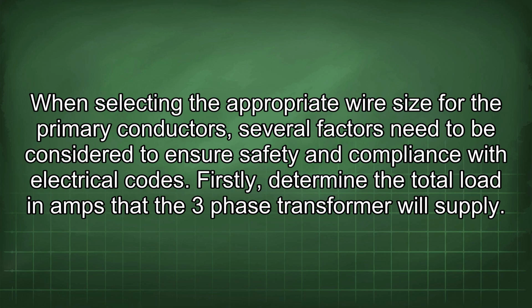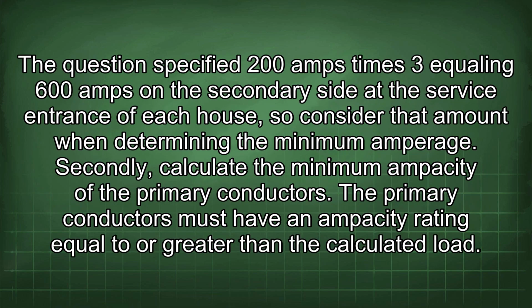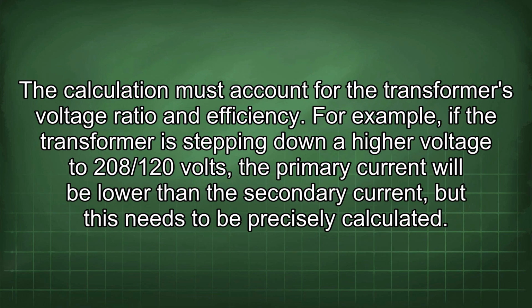When selecting the appropriate wire size for the primary conductors, several factors need to be considered to ensure safety and compliance with electrical codes. Firstly, determine the total load in amps that the three-phase transformer will supply. The question specifies 200 amps times 3 equaling 600 amps on the secondary side at the service entrance of each house, so consider that amount when determining the minimum amperage. Secondly, calculate the minimum ampacity of the primary conductors. The primary conductors must have an ampacity rating equal to or greater than the calculated load. The calculation must account for the transformer's voltage ratio and efficiency.